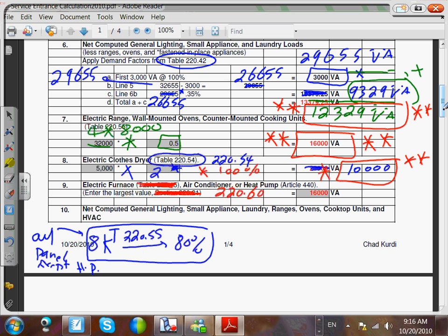Non-coincidental loads. Why non-coincidental loads? Highly unlikely that you're heating the building and cooling it at the same time, unless you're a knucklehead. Right? For non-coincidental loads, DJ, non-coincidental loads could be two pumps for redundancy. One pump is 30 and the other one is 30, and they're sitting in the same well house just for redundancy and for reliability. So if one pump craps out on you, you power the second pump.